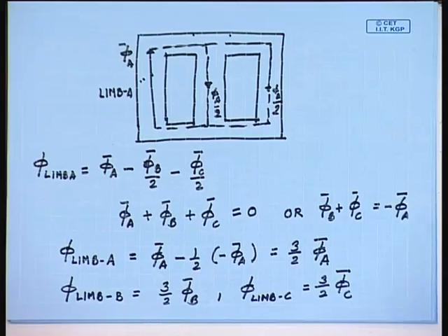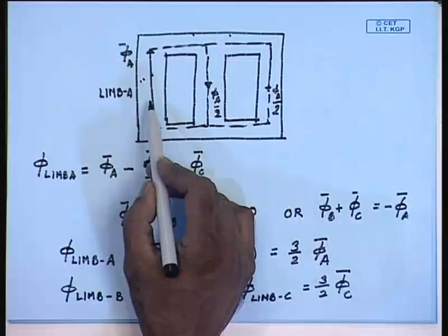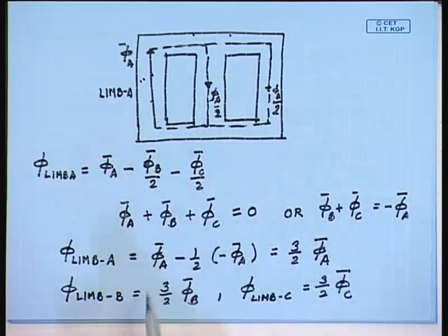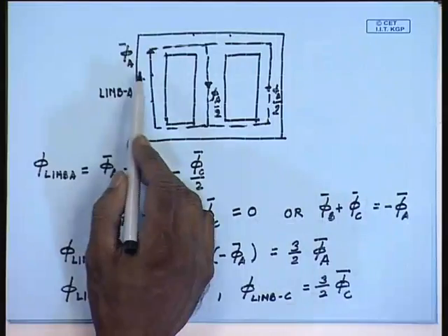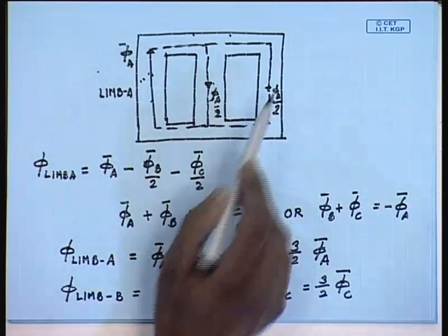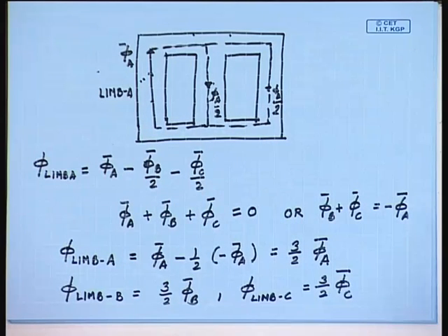Now, this is an important conclusion, an important observation. We find that the flux flowing through the limbs is in fact in phase with the flux produced by the winding on that limb, even when there is mutual coupling between the fluxes. Therefore, the operation of the coils on individual limbs will be independent of each other as long as this relationship, that is the balanced voltage relationship, is maintained.